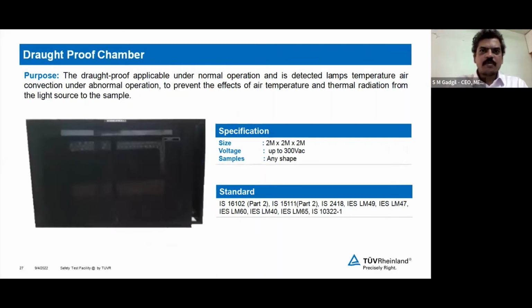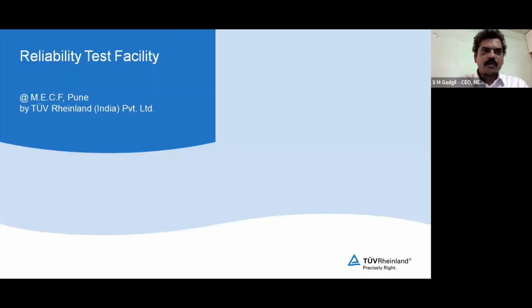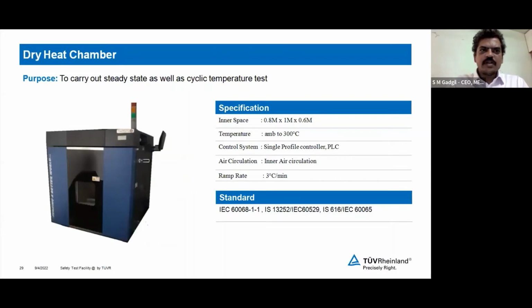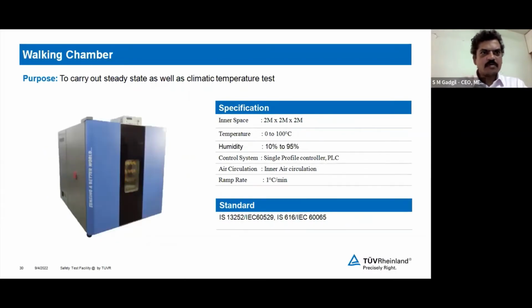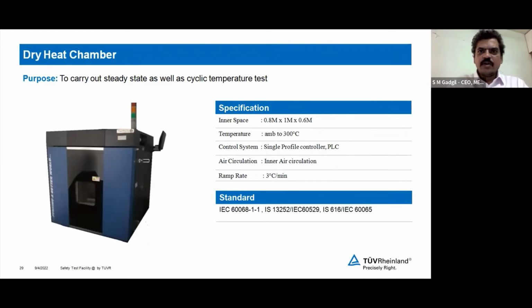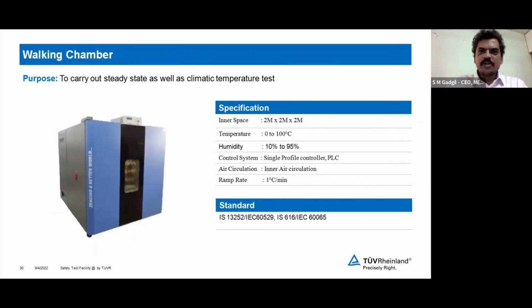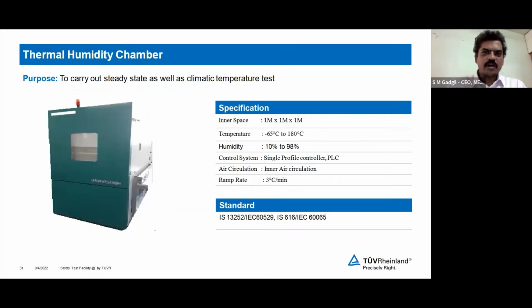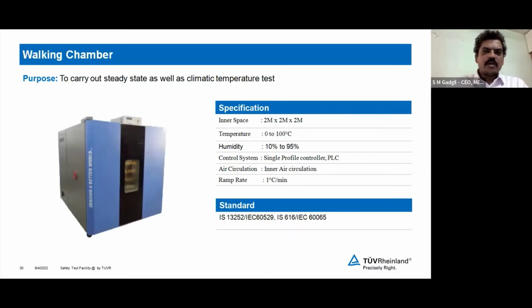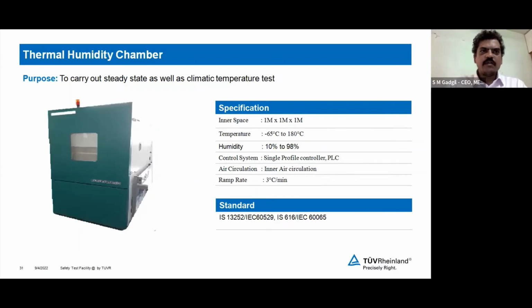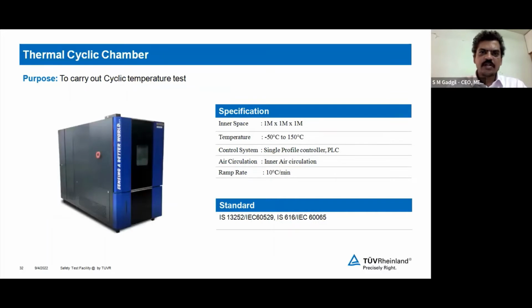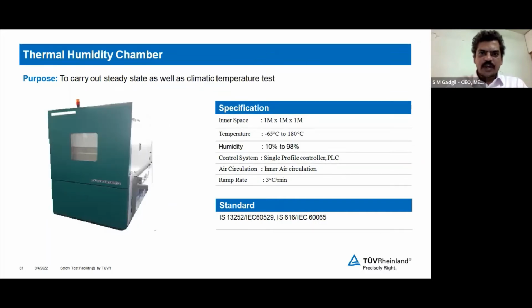So this is a draught proof chamber, reliability test facility. Now the chamber part comes, dry chamber. We are having a walk-in chamber, 2 meter by 2 meter by 2 meter, temperature range 0 to 100 and humidity 10 to 95%. Then we have a thermal humidity chamber, -65 to 180 degrees Celsius, and humidity 10 to 98%.